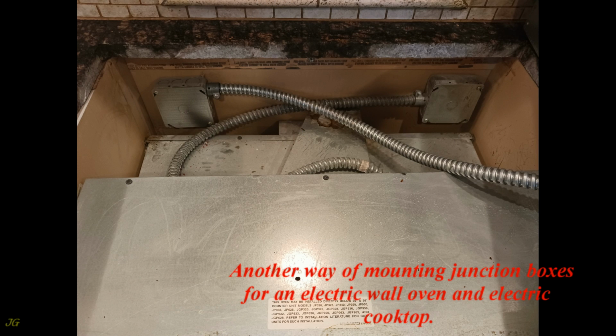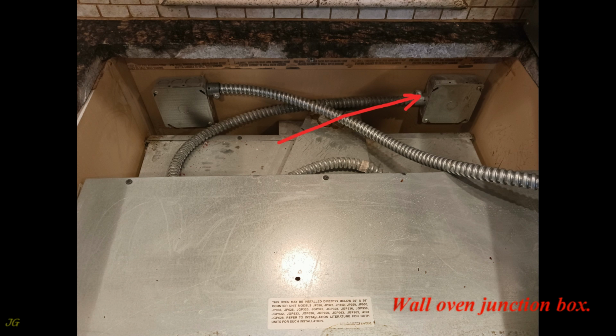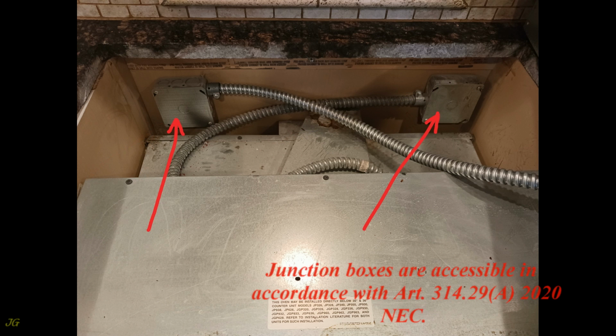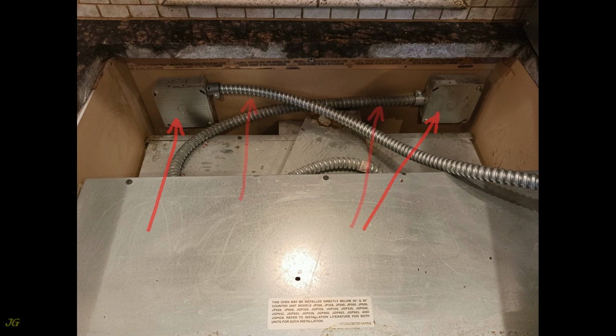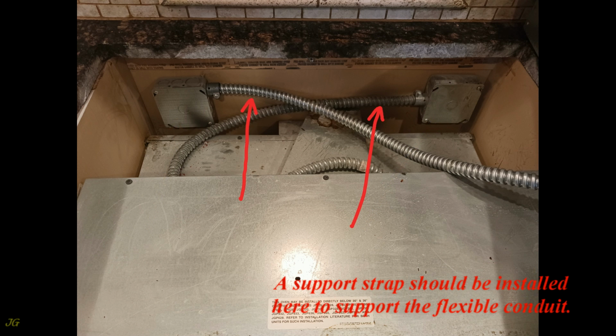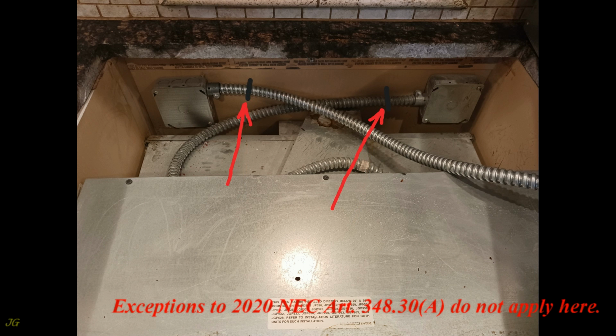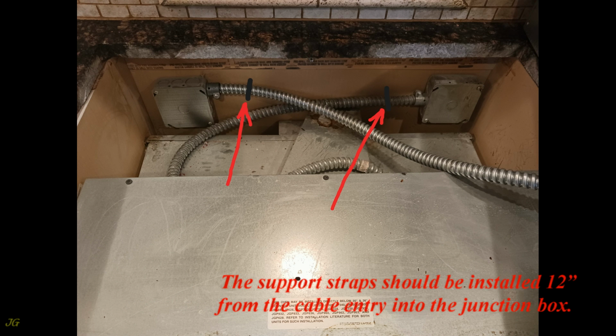Another way of mounting junction boxes for an electric wall oven and electric cooktop. Wall oven junction box. Cooktop junction box. Junction boxes are accessible in accordance with Article 314.29 A, 2020 NEC. A support strap should be installed here to support the flexible conduit. Exceptions to 2020 NEC Article 348.30 A do not apply here. The support straps should be installed 12 inches from the cable entry into the junction box.